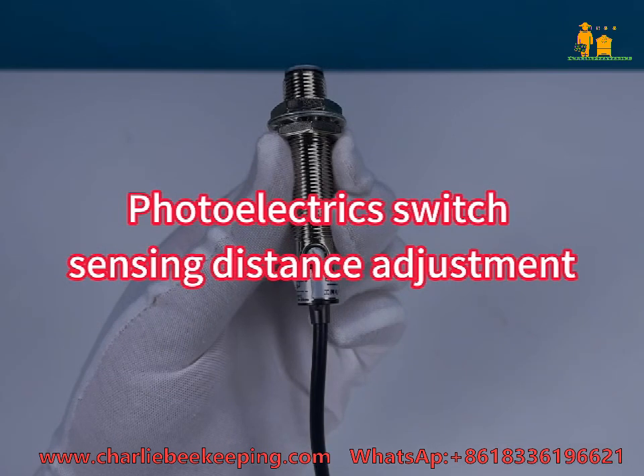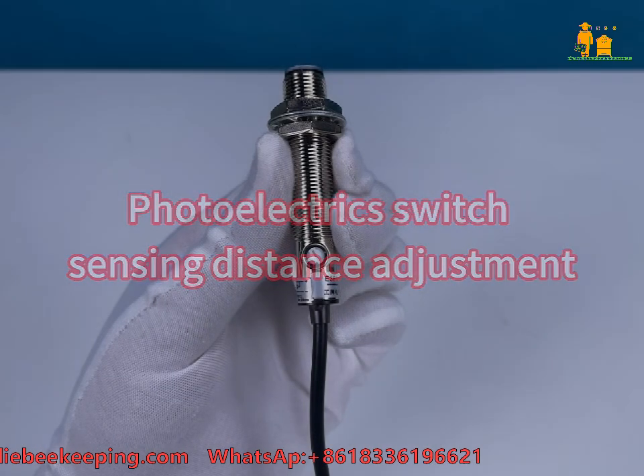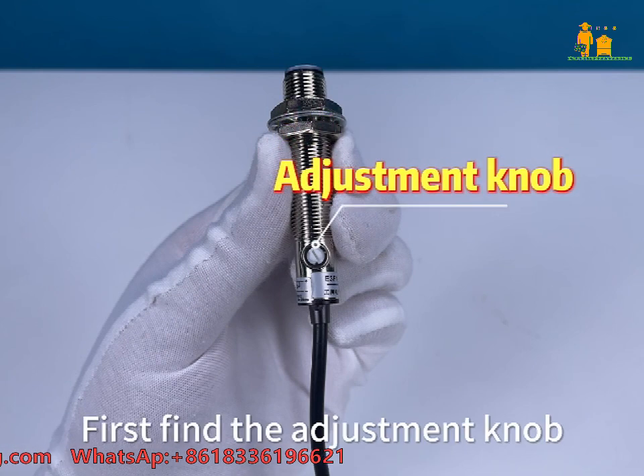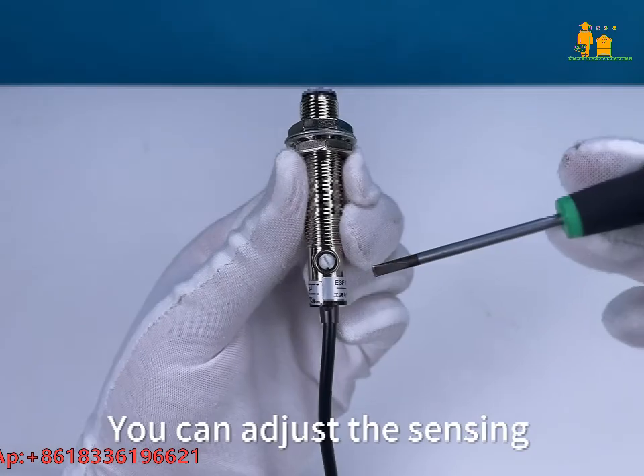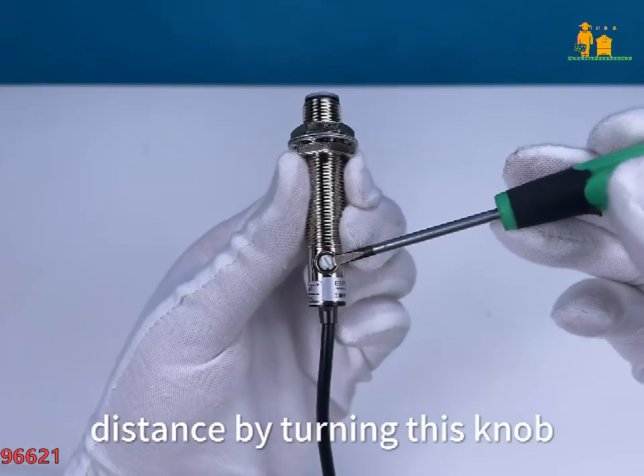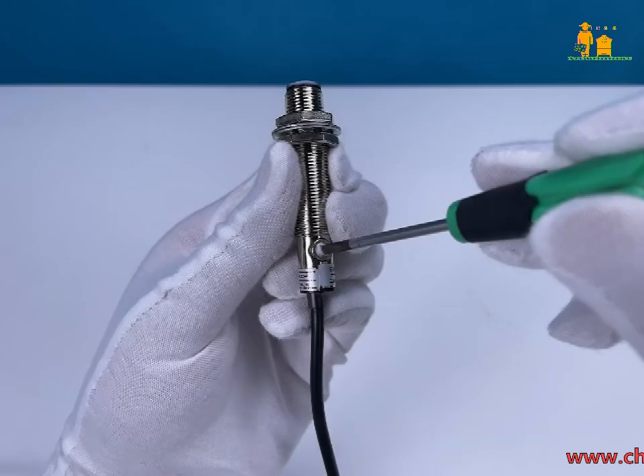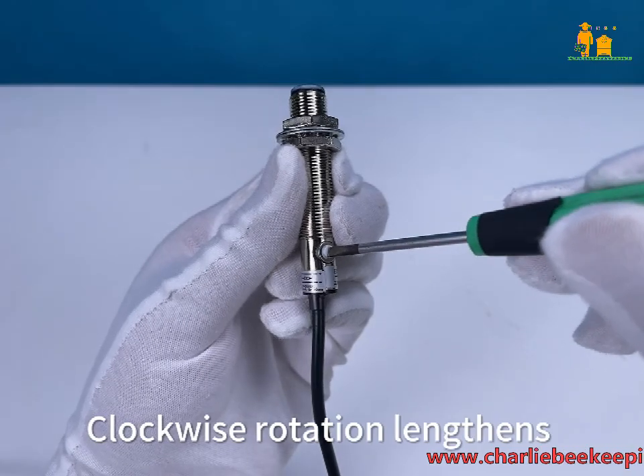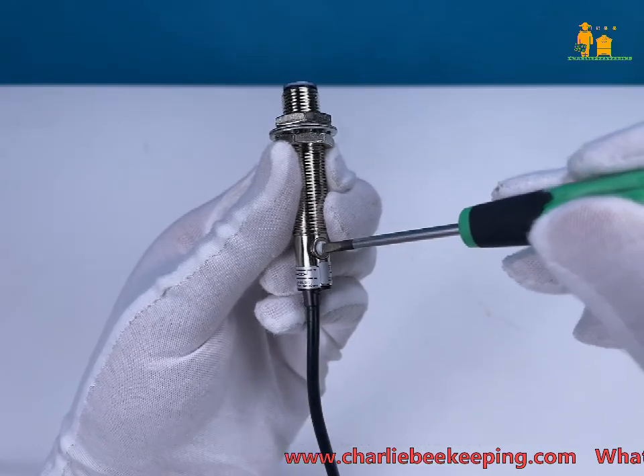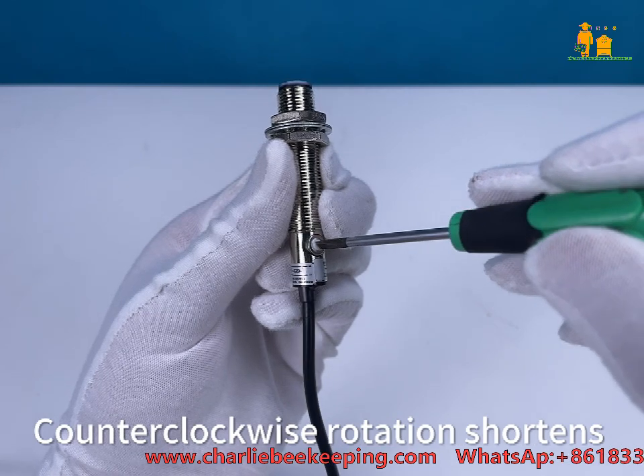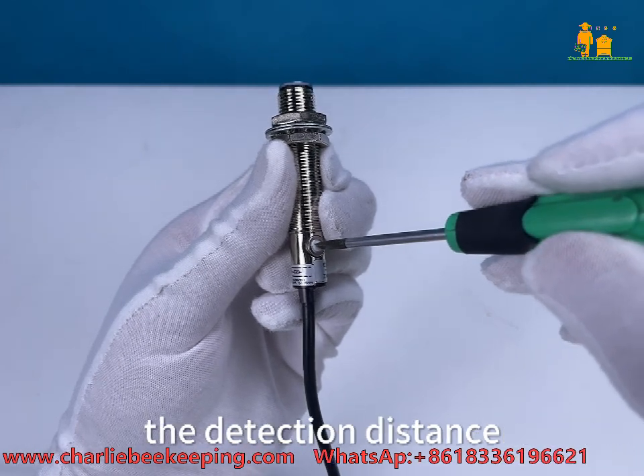Photoelectric switch, sensing distance adjustment. First find the adjustment knob. You can adjust the sensing distance by turning this knob. Clockwise rotation lengthens the detection distance. Counterclockwise rotation shortens the detection distance.